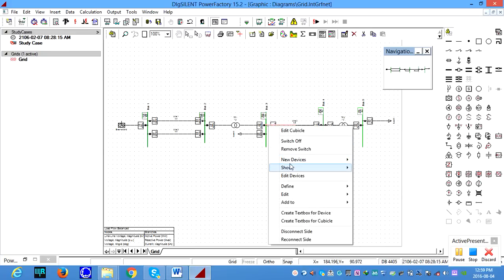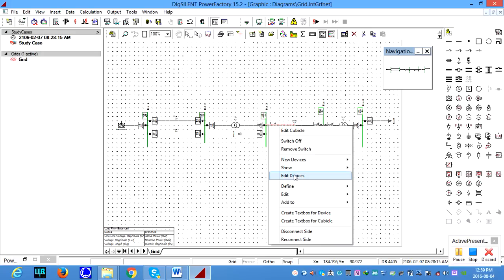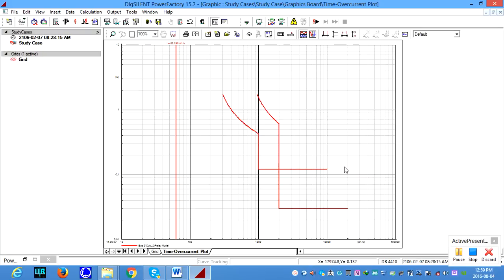You right click on the cubicle where we have your relay models and select show and include time overcurrent plot. But you can see the load current is 62 amperes. It means the relay is not tripping. So we want to know which one is definite and the other one, and it is better to add labels for these characteristics. To add the labels, select a specific curve. And you can go to add the labels here.